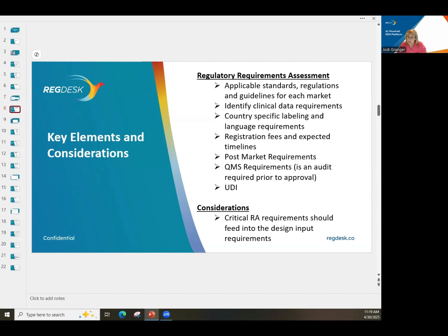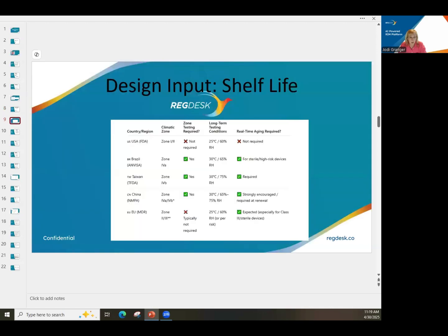The best scenario is that once you've identified these markets, the critical RA requirements are then factored into your design input document. So if you have a shelf life requirement, as an example, where you need to go in specific zones, then you should have that in your design input document. That's what you should be developing your product to meet. So it's important to do that.